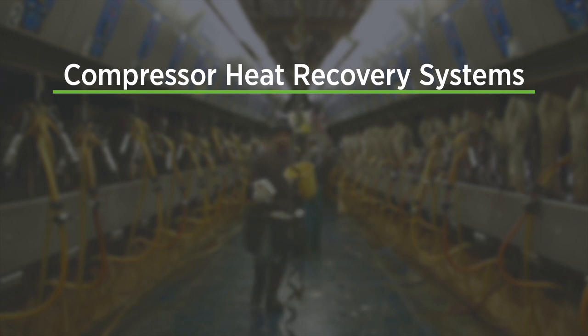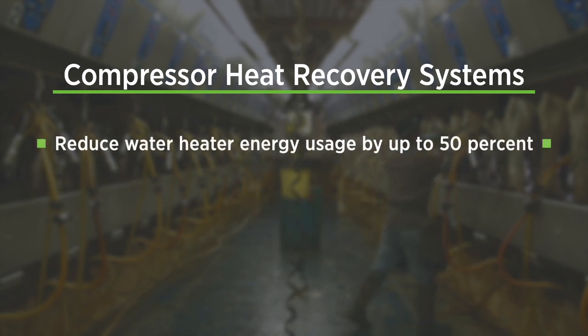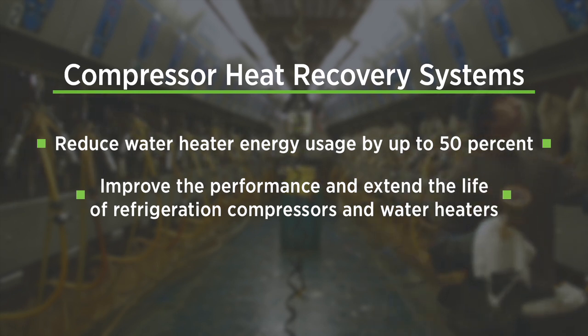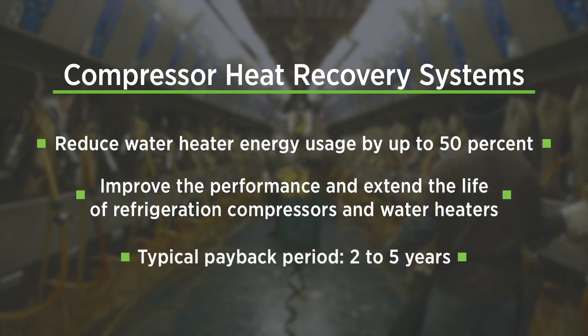Compressor heat recovery systems can cut water heating costs by up to 50%, and by reducing the load on both the milk cooling system and the water heater, heat recovery units can both improve their performance and extend their life. They typically pay for themselves in two to five years with no financial assistance.